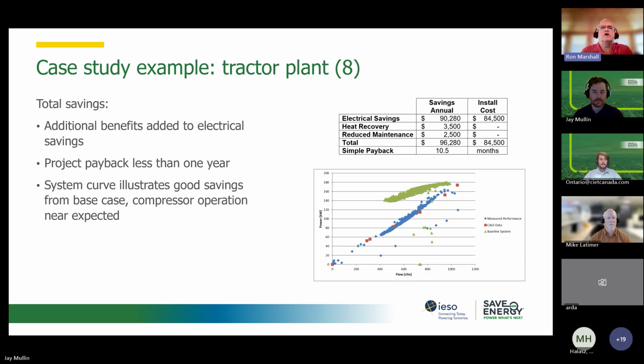Now this chart on the bottom right is a system curve, and that's a good thing that you can do with data collected, the time-based data. You can do a scatter plot like this. So the light green up at the top was the old system, how it varied, not very close to the one-to-one turn down, right? So they could have fixed their leaks and only gained a fraction of the savings from their efforts with the old system.